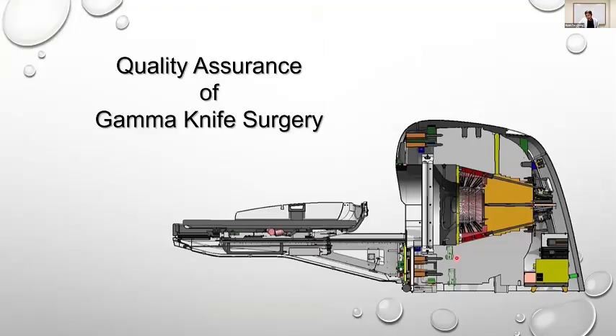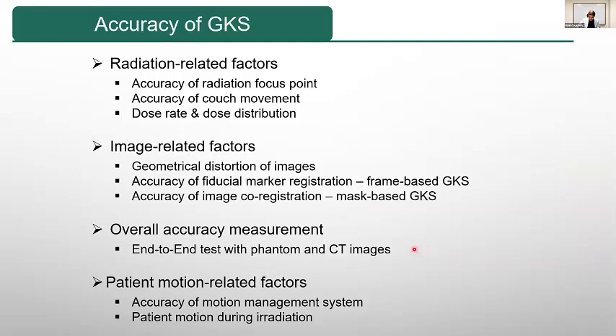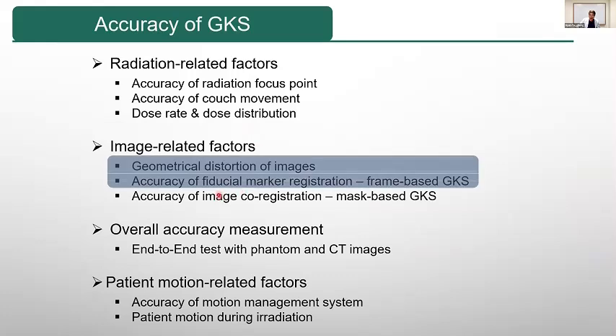Okay, it's time to look at the gamma knife as a medical physicist. Until now, we have seen the clinical examples, but from now on, I will talk about the quality assurance activities of the gamma knife machine itself. In the quality assurance of gamma knife surgery, there are radiation-related factors like mechanical accuracy, dose distributions and dose rate measurement. And among the image-related factors, I will mention only the accuracy of image co-registration for the mask-based system and overall accuracy measurement. I mean, an end-to-end test with phantom and CT images will be given.